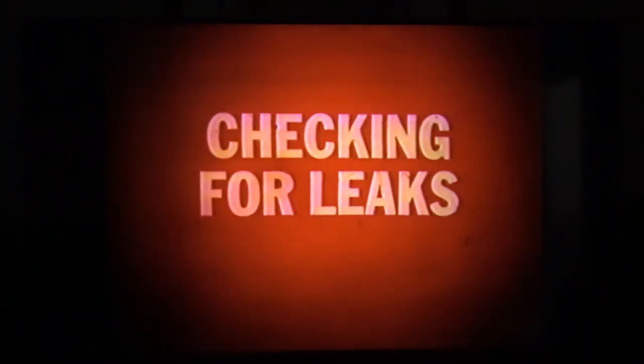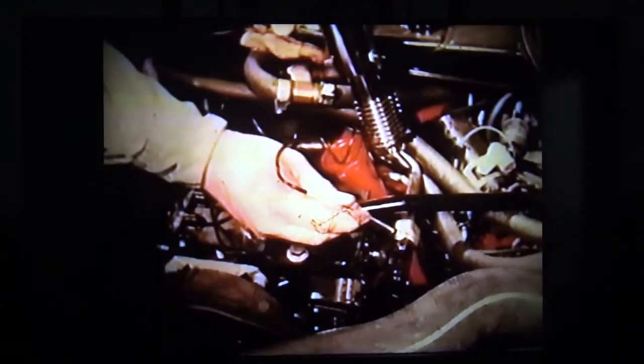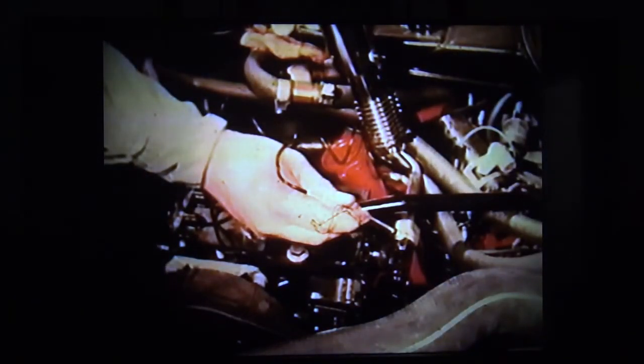Before replacing the receiver dryer, the system should be checked for leaks. Let the air conditioner run and check the system for leaks with a leak detector. Check the manufacturer's operating instructions for the leak detector you are using. When using an electronic leak detector, calibrate the detector according to the instructions and check for leaks at a rate of 1 inch per second.